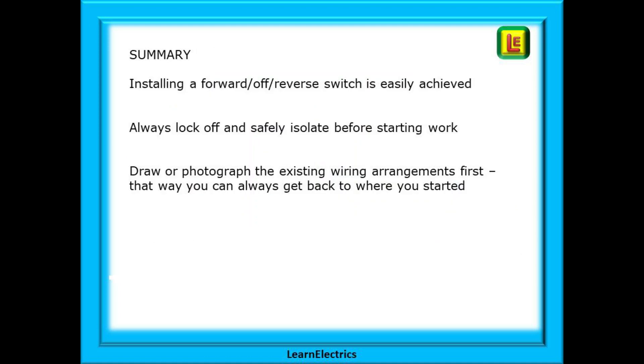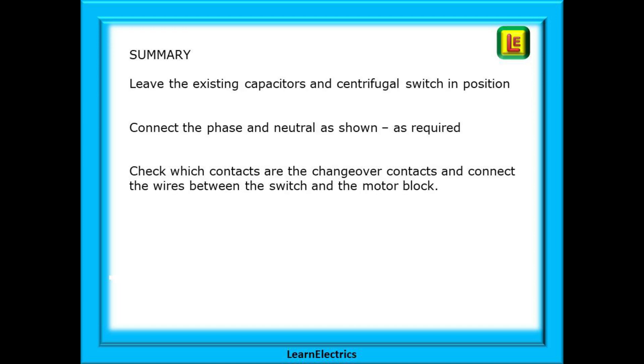A little summary of what we have done. Installing a forward off reverse switch is easily achieved. Always lock off and safely isolate before starting work. Draw or photograph the existing wiring arrangements first. That way you can always get back to where you started. Leave the existing capacitors and centrifugal switch in position. Connect the phase and neutral as shown as required. Check which contacts are the changeover contacts and connect the wires between the switch and the motor block. And that is it. Installing a forward and reverse switch really is a simple task. As always proper preparation is essential.